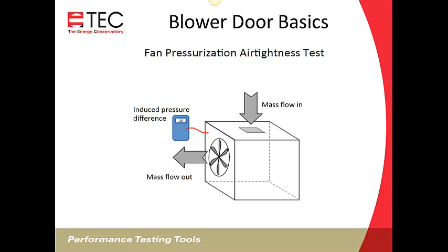If you're entering the baseline into your gauge, that essentially zeroes that out. So if you have a baseline of -5, it subtracts that -5, and so the pressure being displayed on your gauge is the induced pressure.